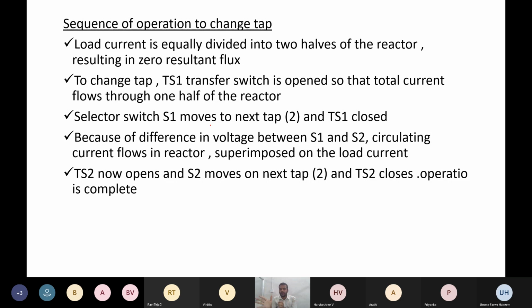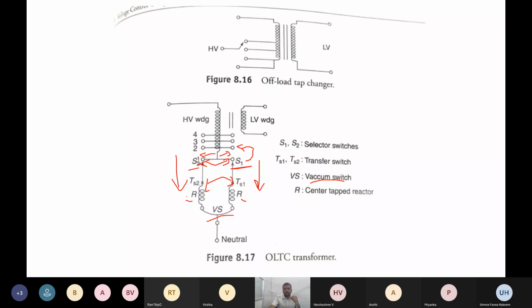TS1 we close after the position change. So here TS2 should be opened and S2 moves on to tap 2. That means S1 has moved, and now TS2 has to be opened. So always remember, before you change the tap, you have to open the transfer switches, because we need to limit the current. We have to limit the flow of current into the positions.